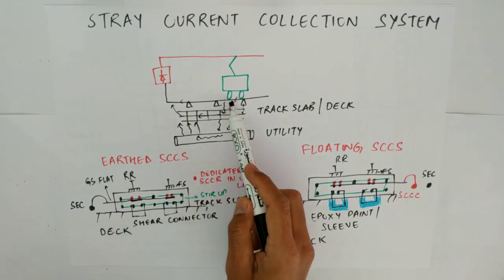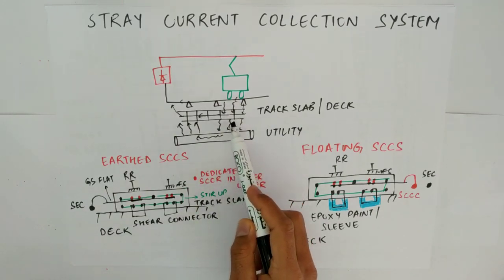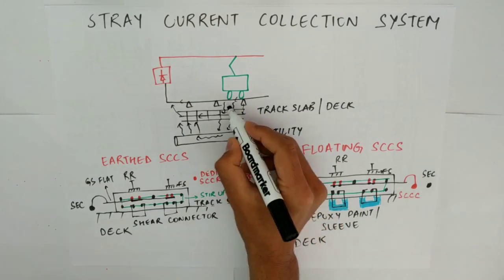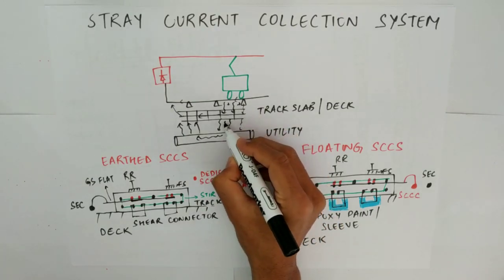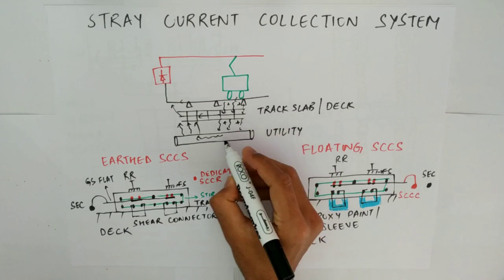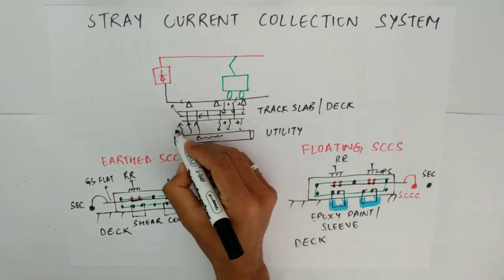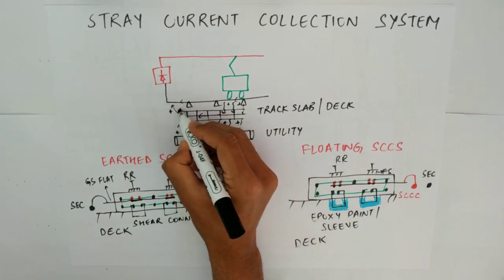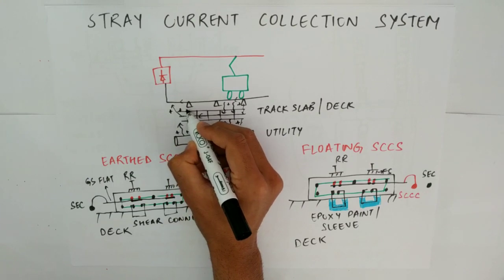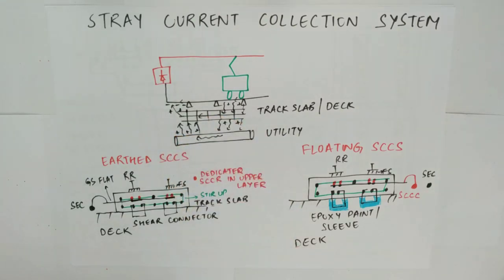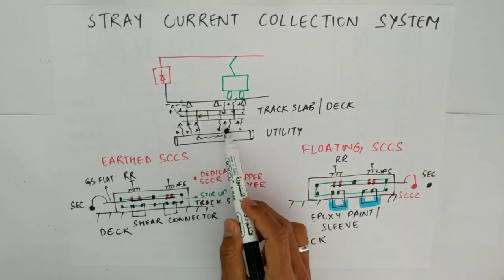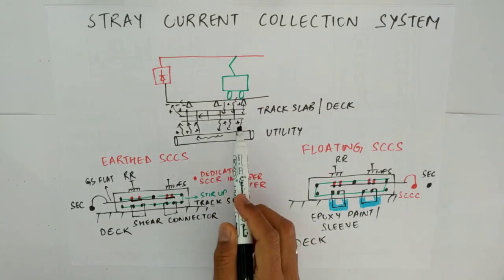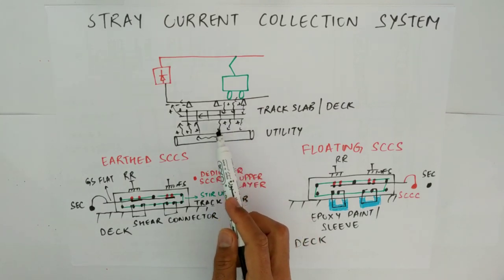Due to this leakage of current, this location becomes anodic and corrosion starts happening at these locations whenever the current is leaving the structure. So whenever the current is leaving the structure, corrosion will happen there — this we have discussed in lectures 1, 2 and 3.